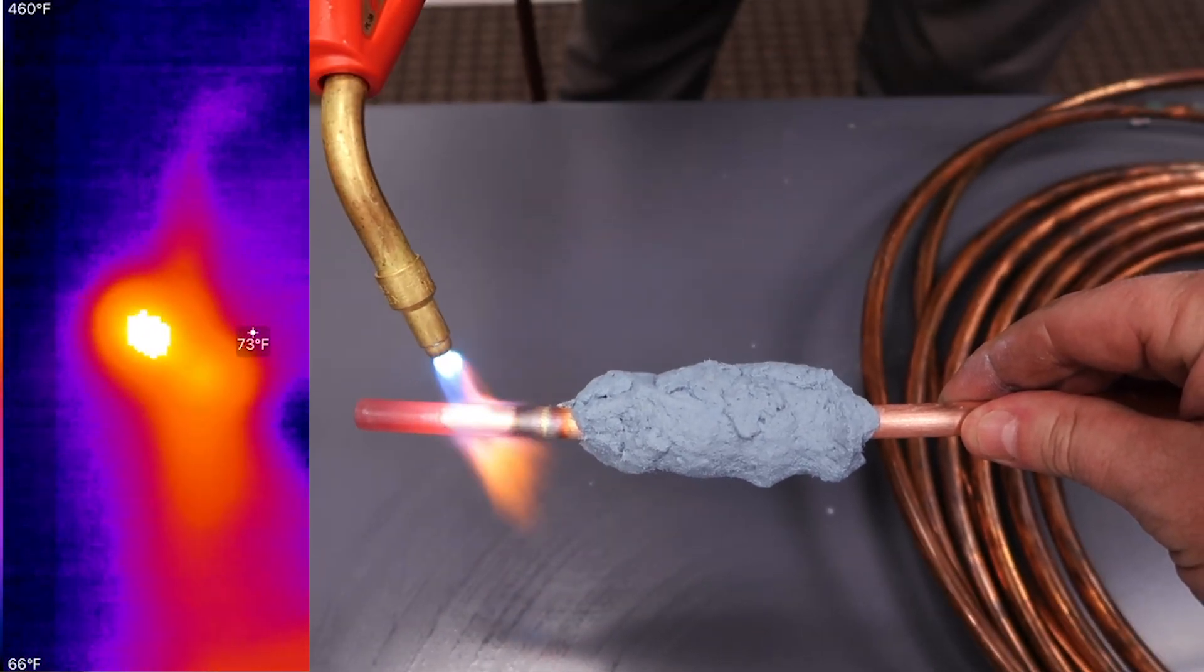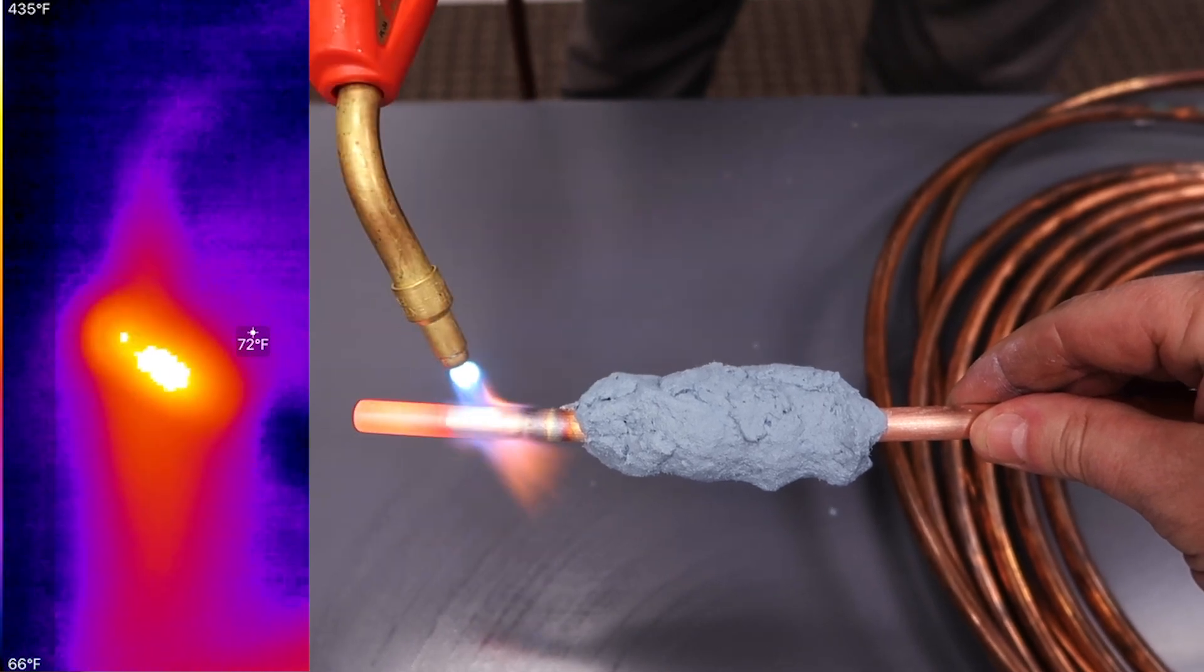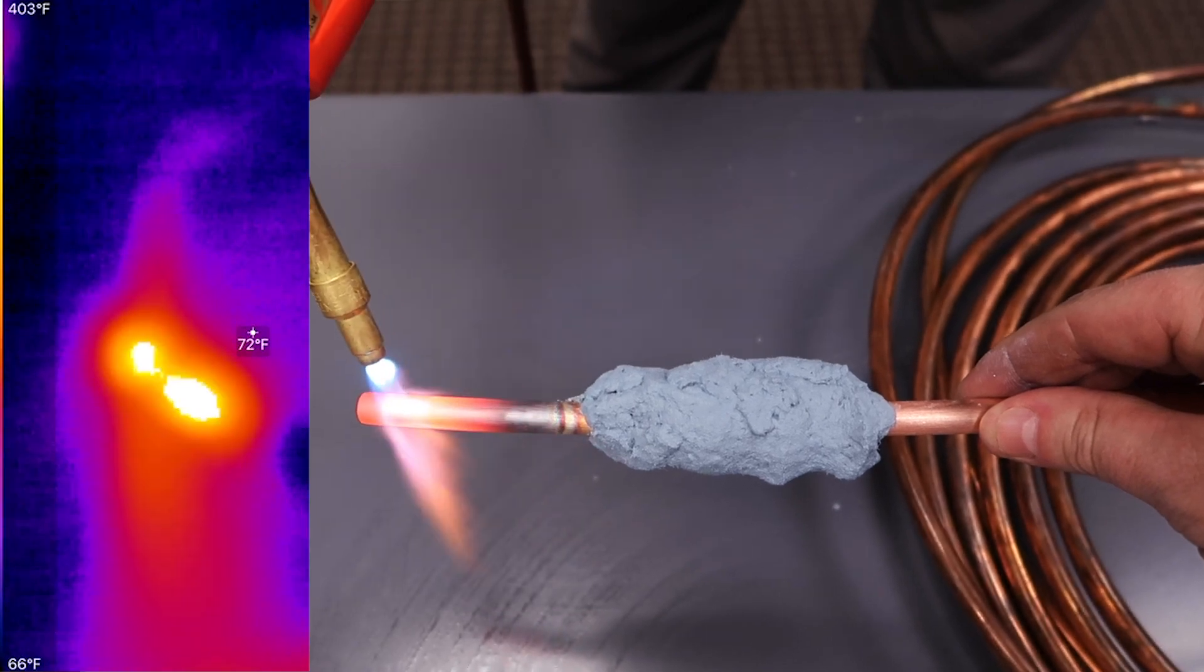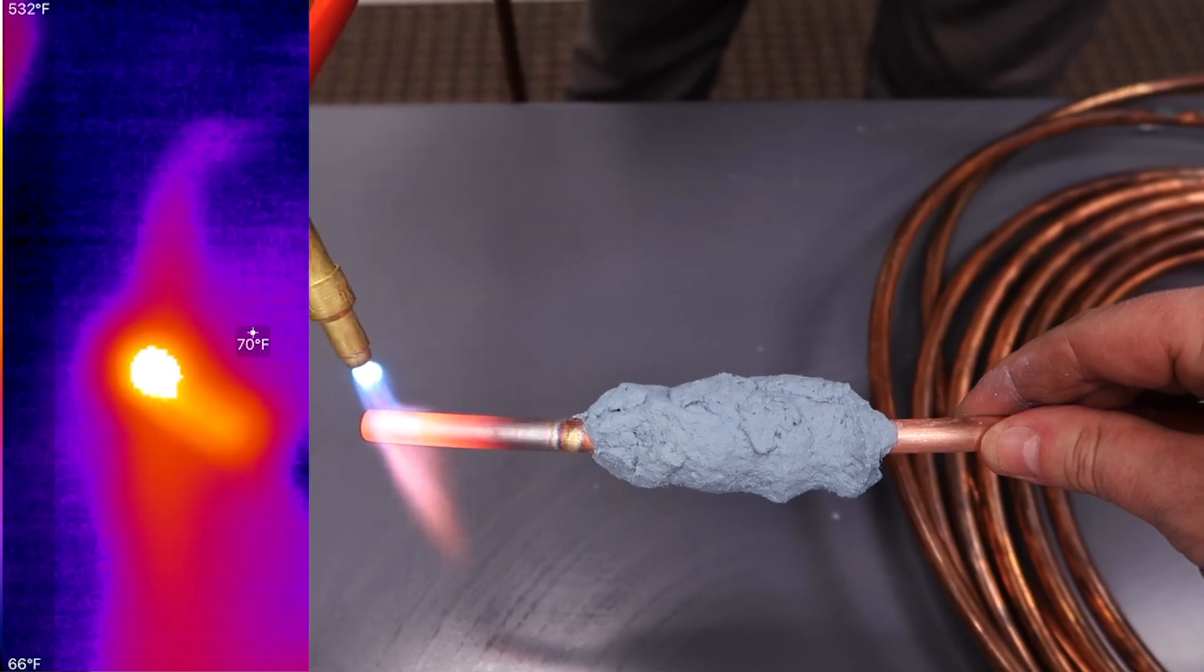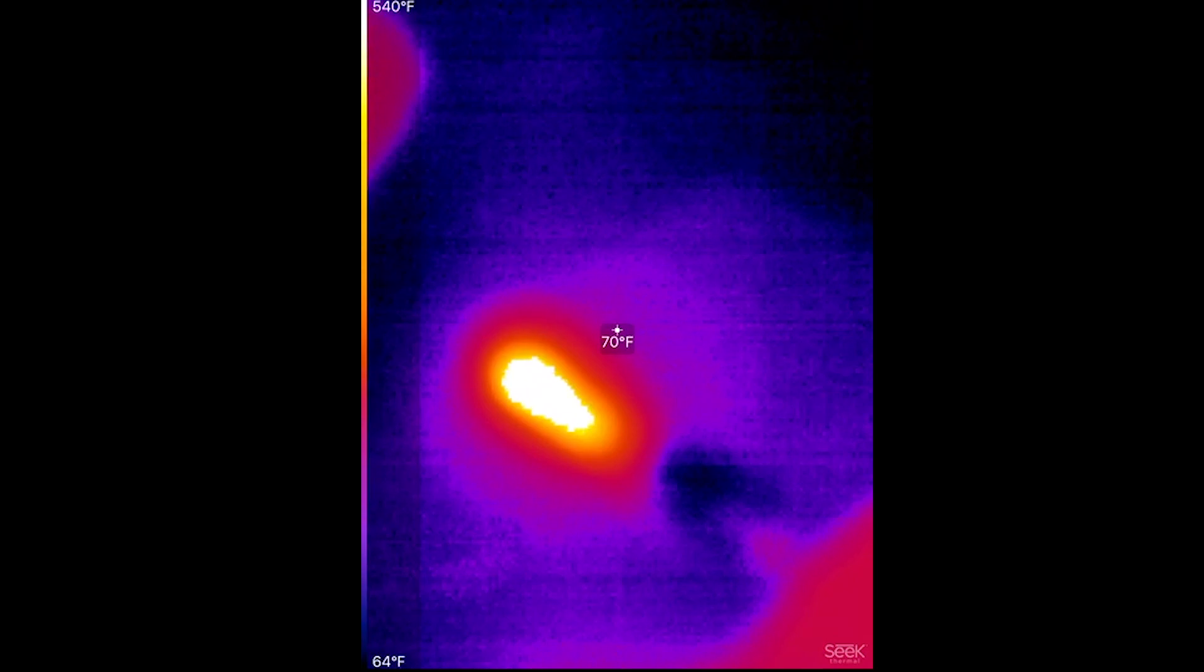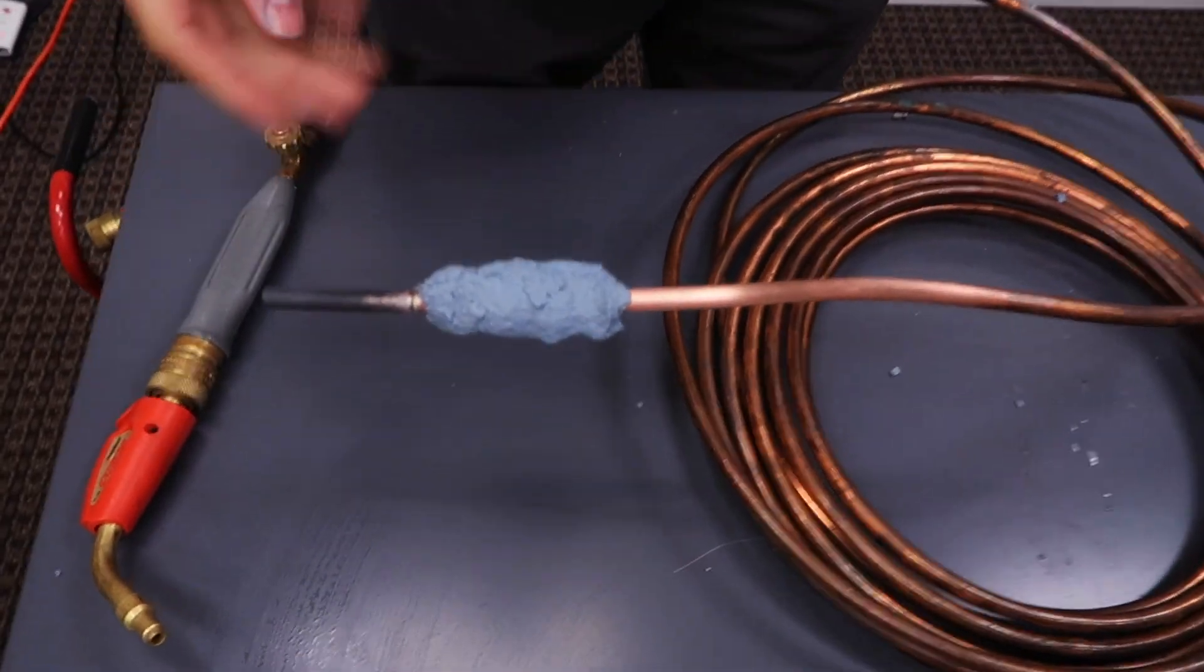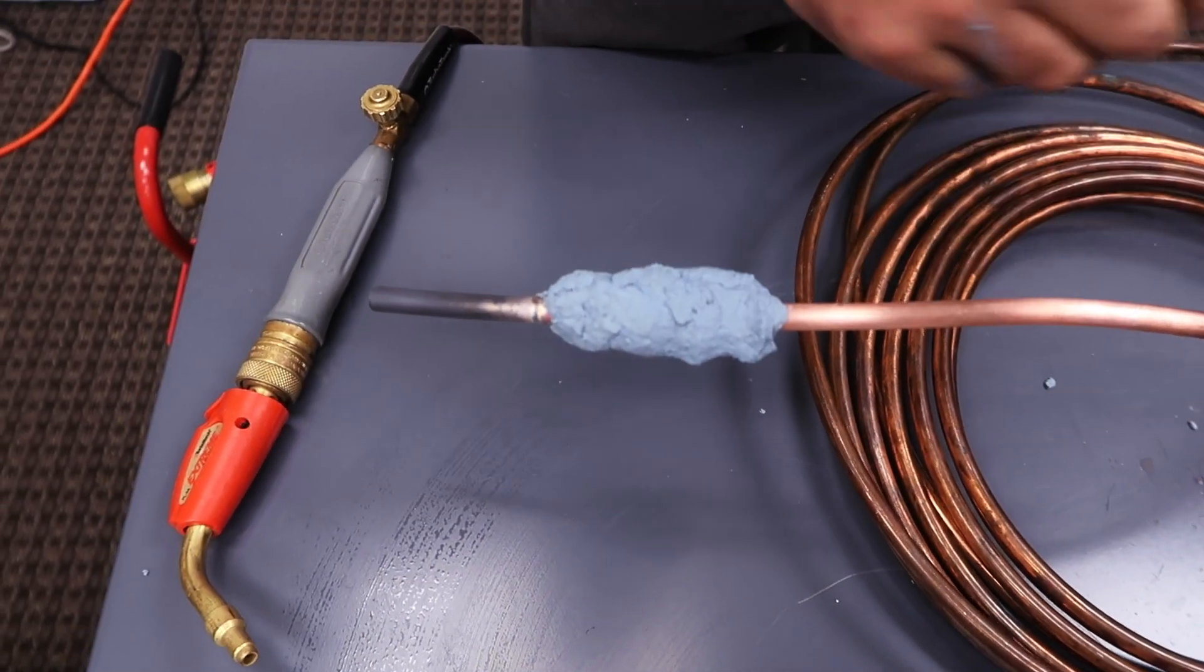So this will protect any type of TXVs that you're working with, or any type of metering device or valves that you're working near to make sure that that heat does not transfer over to those valves to destroy them. Again, this is to protect the areas that you're working in and making sure the heat is concentrated in one area only.